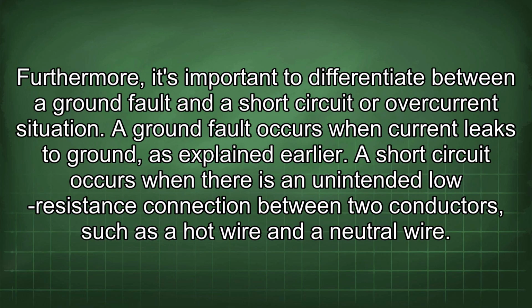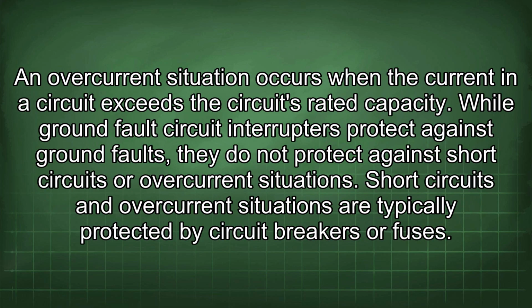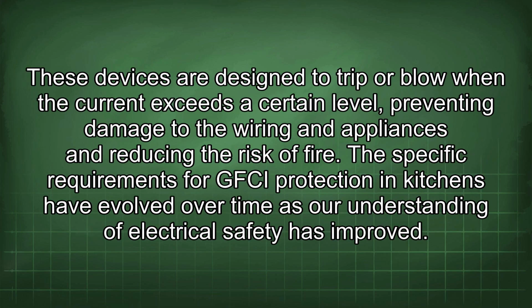Furthermore, it's important to differentiate between a ground fault and a short circuit or overcurrent situation. A ground fault occurs when current leaks to ground, as explained earlier. A short circuit occurs when there is an unintended low resistance connection between two conductors, such as a hot wire and a neutral wire. An overcurrent situation occurs when the current in the circuit exceeds the circuit's rated capacity. While ground fault circuit interrupters protect against ground faults, they do not protect against short circuits or overcurrent situations. Short circuits and overcurrent situations are typically protected by circuit breakers or fuses. These devices are designed to trip or blow when the current exceeds a certain level, preventing damage to the wiring and appliances and reducing the risk of fire.